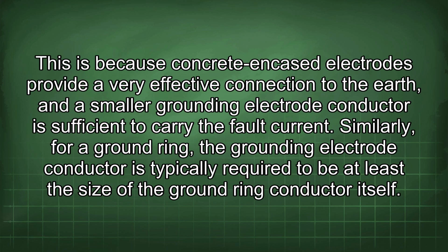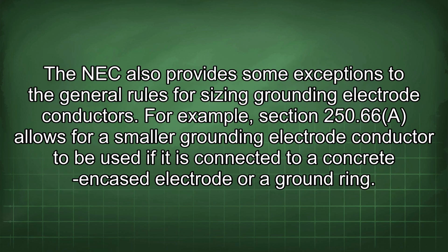This is because concrete encased electrodes provide a very effective connection to the earth, and a smaller grounding electrode conductor is sufficient to carry the fault current. Similarly, for a ground ring, the grounding electrode conductor is typically required to be at least the size of the ground ring conductor itself. The NEC also provides some exceptions to the general rules for sizing grounding electrode conductors.